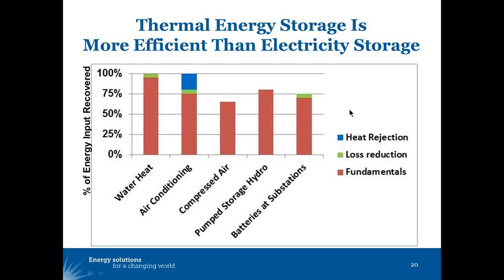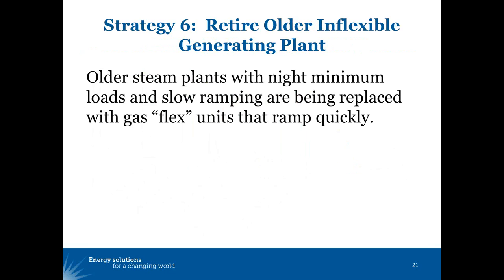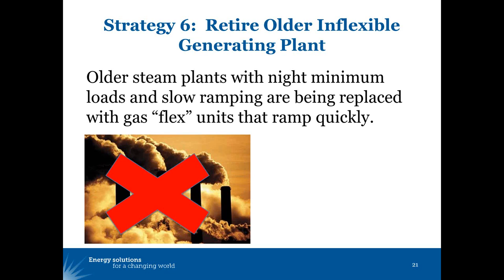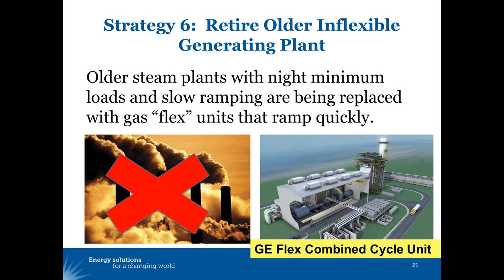There are 45 million electric water heaters in the United States and nearly the same number of electric air conditioners. These thermal storage techniques are huge opportunities, so I've spent more time on them than any of the others. The sixth strategy is retire older inflexible generating plant. Old steam plants have to run at some minimum load all night in order to be available to ramp up during the day. They are being replaced really quite quickly with natural gas flex units that ramp up more quickly. So, this era is going behind us, and the GE flex combined cycle unit that can ramp up from 0 to full output in about 15 minutes is becoming a tremendous opportunity.